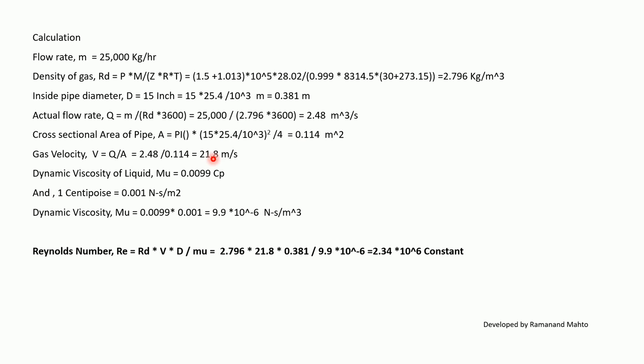Dynamic viscosity of gas: 0.0099 cP, and since 1 centipoise = 0.001 N·s/m², dynamic viscosity = 0.0099 × 0.001 = 9.9 × 10⁻⁶ N·s/m². Reynolds number Re = ρ × V × D / μ = 2.796 × 21.8 × 0.381 / (9.9 × 10⁻⁶) = 2.34 × 10⁶, which is turbulent flow.